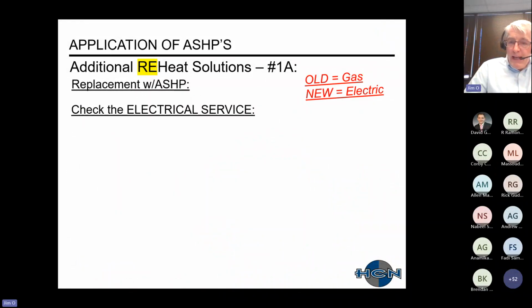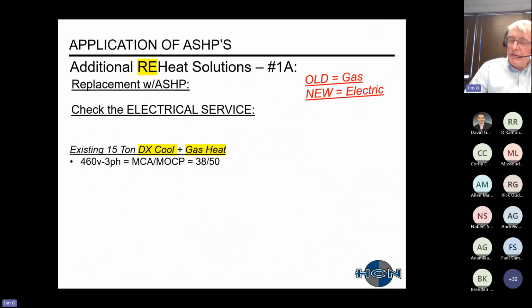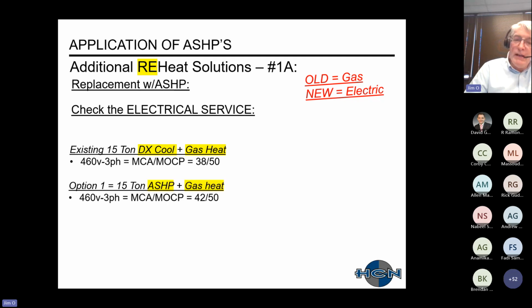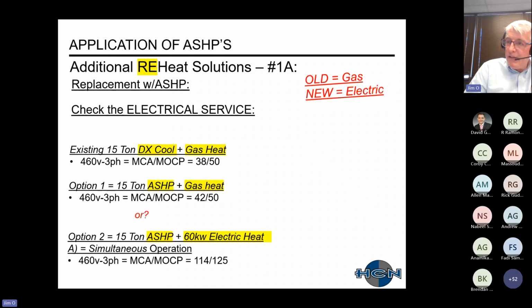Now, if we're taking an existing unit that has gas and then switching to electric, just running a couple different scenarios, this is a 15-ton existing unit with that electrical service. If we had gas heat, our MCA went up, maybe with some changes to our compressors, et cetera, over a span of 10 or 15 years. But what becomes problematic is that if you take an air source heat pump and change it to electric heat, you can see the difference in the electrical service is extraordinary.